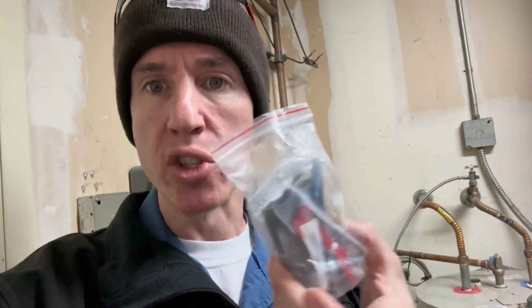I'll just wait till the problem gets so bad that it fails every single time that it gets reset, or the customer wants to start randomly replacing parts without knowing for sure what the actual issue is. So I said all that and then spoke to the customer, and they want to swap out the ice thickness probe as a precaution. It's something that I recommended to them, that hey, just because it's working right now doesn't mean it won't fail in the future.